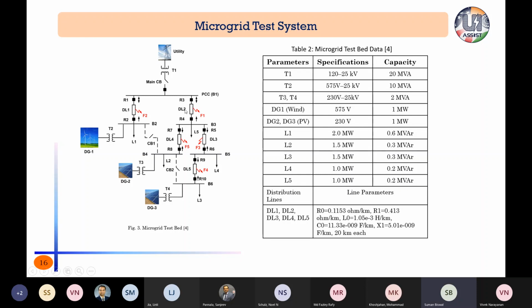Here we have 5 lines, so faults are conducted in each of the lines. We have considered the 3-phase balanced fault in the middle of the line. Since it is a microgrid, it is assumed that the lines are short, so the fault at the midpoint is made, and because there will not be any appreciable change in the current, by taking that assumption we introduced the fault at the middle of the line.